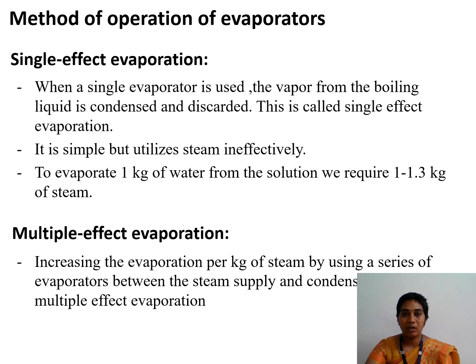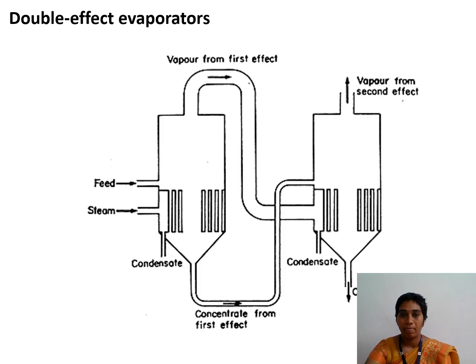A single effect evaporator has only one evaporator — it is simple to use but has inefficient operation. To evaporate 1 kg of water, it requires 1 to 1.3 kg of steam. In a multiple effect evaporator, using 1 kg of steam can evaporate around 0.7 to 0.8 kg of water more efficiently. A double effect evaporator has 2 evaporators.